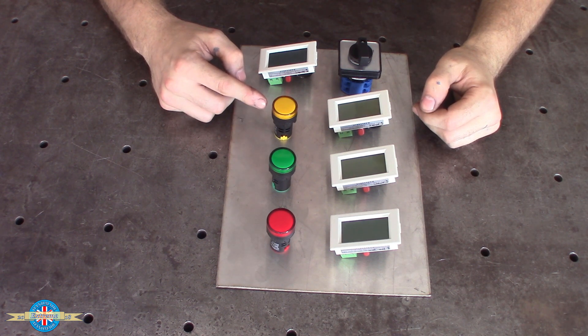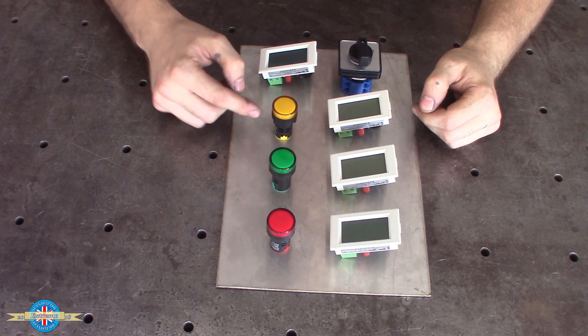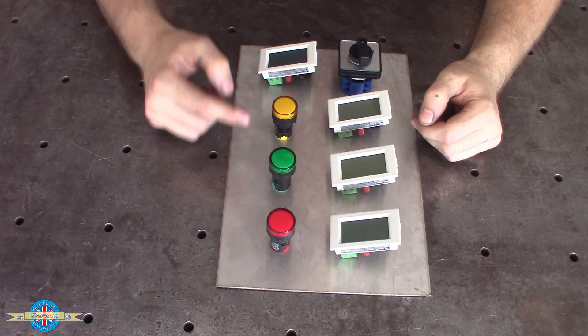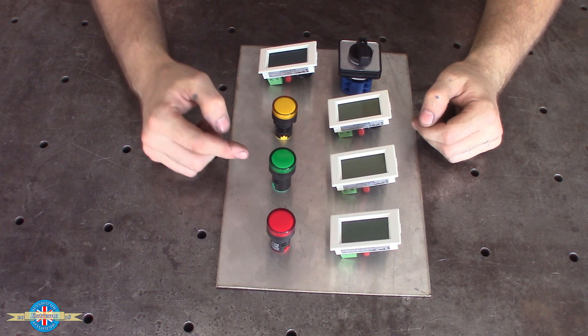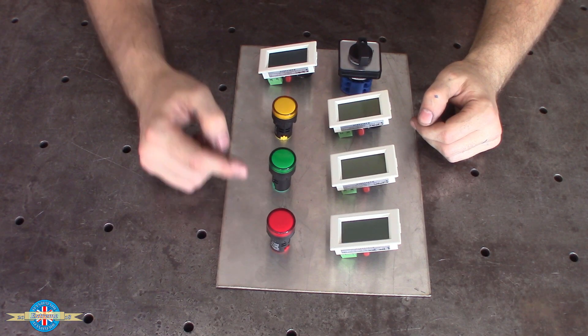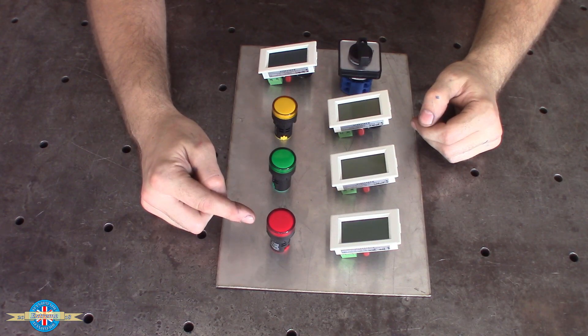The orange light tells me that the control gear inside the enclosure has put the motor into what's known as the star configuration. After about a second, the control gear switches over to what's known as the delta, and the green light will come on and the orange light will go off. Now if for some reason there's an overcurrent situation, neither of these lights will be on and the red light will come on to tell me that there's a fault.